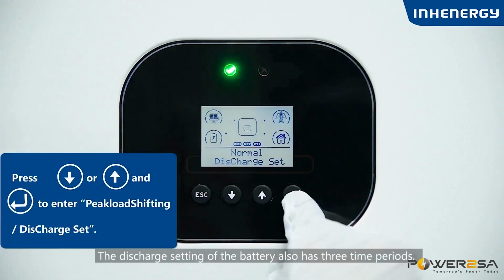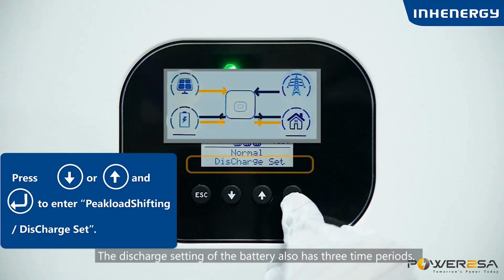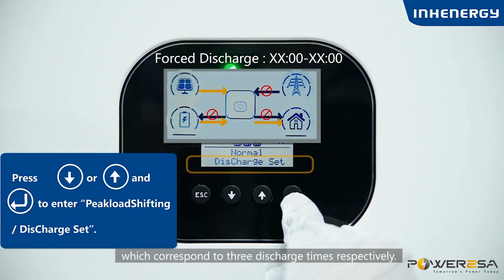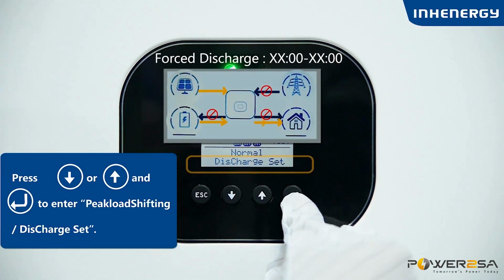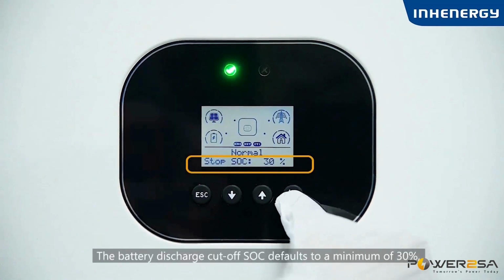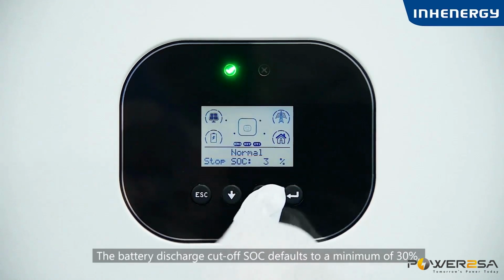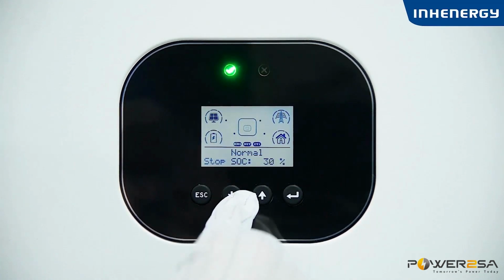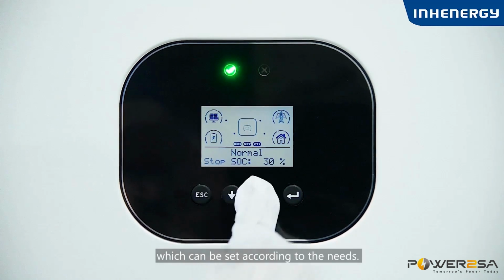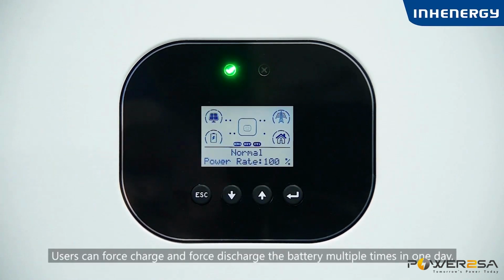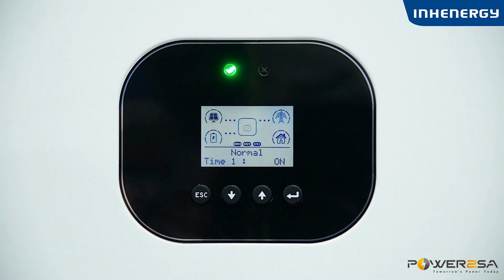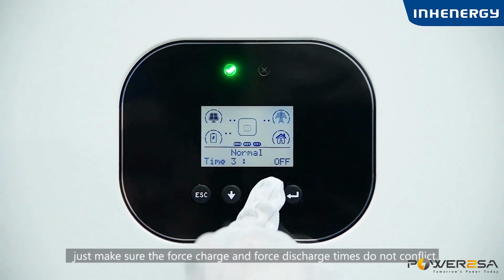The discharge setting of the battery also has 3 time periods, which correspond to 3 discharge times respectively. The battery discharge cutoff SOC defaults to a minimum of 30%, which can be set according to the needs. Users can force charge and force discharge the battery multiple times in one day. Just make sure the forced charge and the forced discharge times do not conflict.